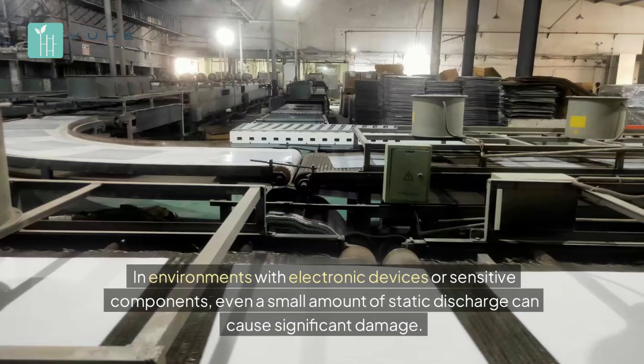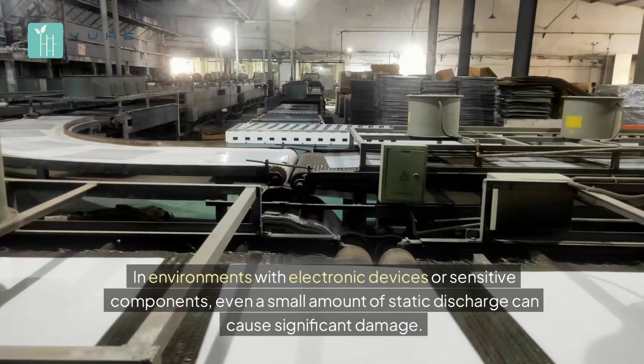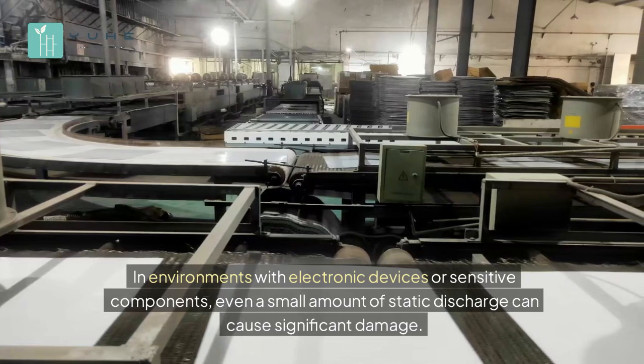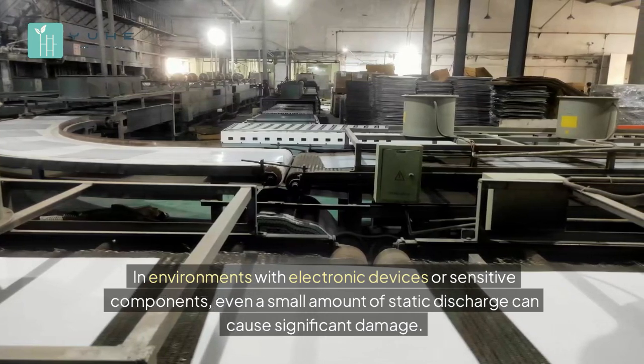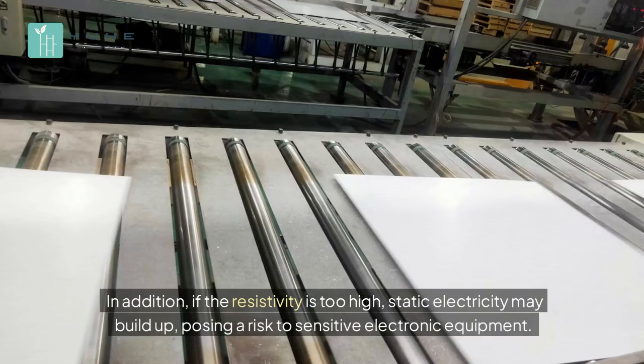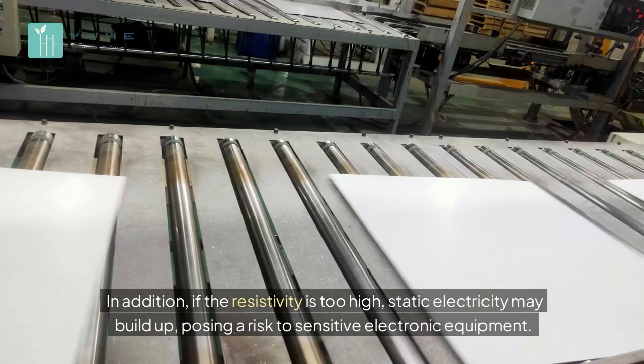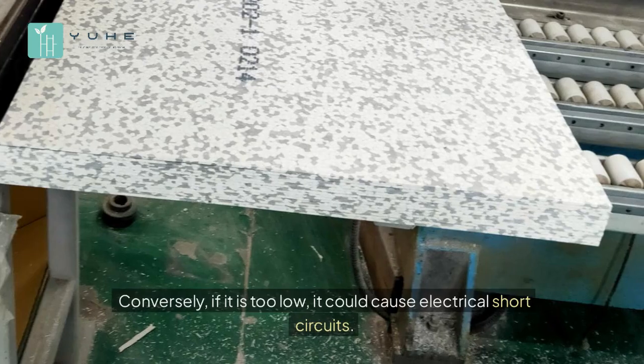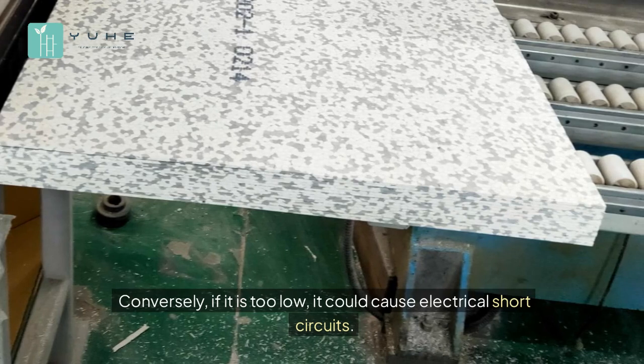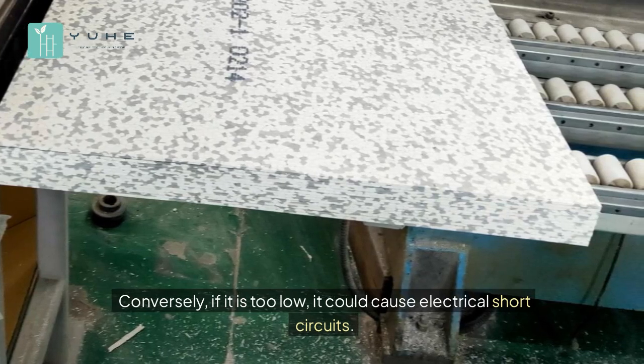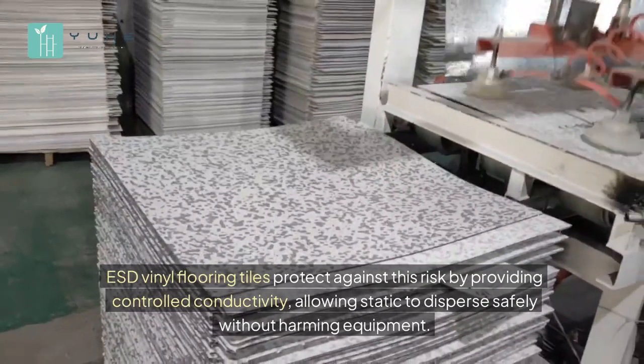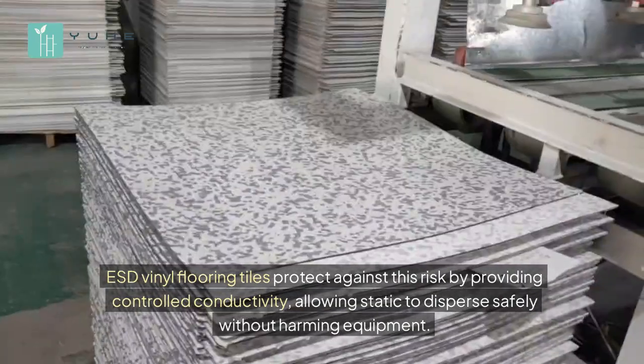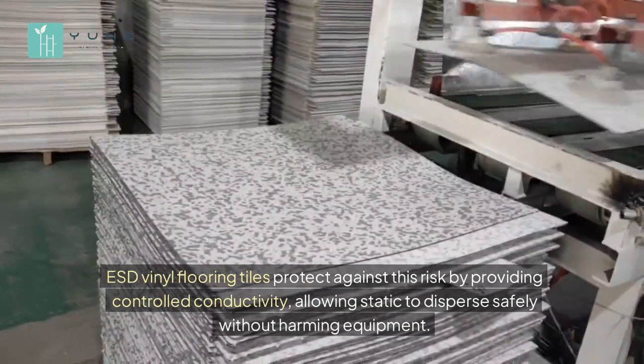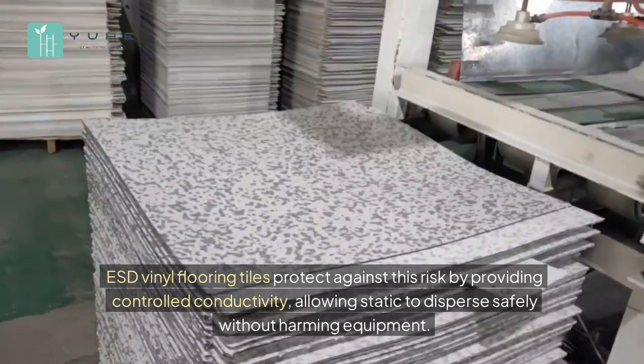Why is ESD resistance important? In environments with electronic devices or sensitive components, even a small amount of static discharge can cause significant damage. In addition, if the resistivity is too high, static electricity may build up, posing a risk to sensitive electronic equipment. Conversely, if it is too low, it could cause electrical short circuits. ESD vinyl flooring tiles protect against this risk by providing controlled conductivity, allowing static to disperse safely without harming equipment.